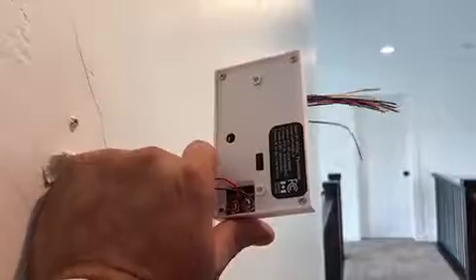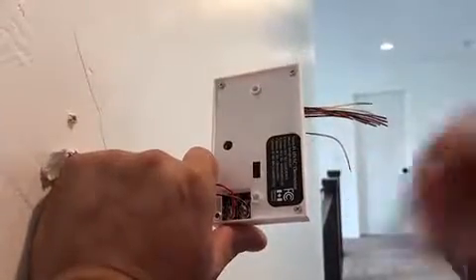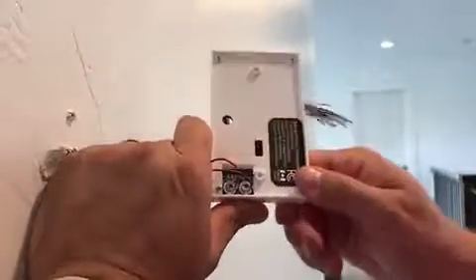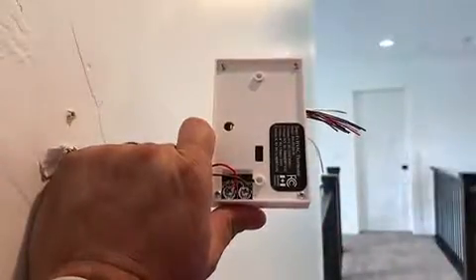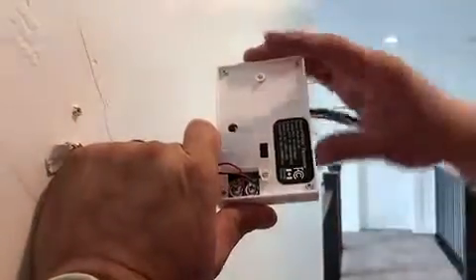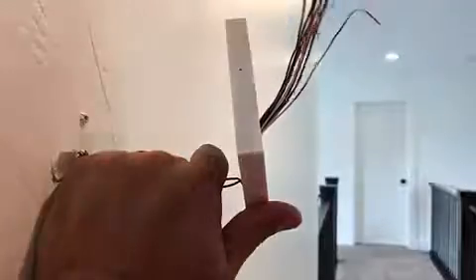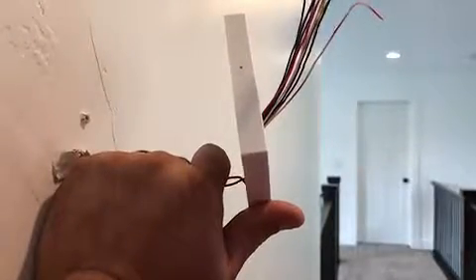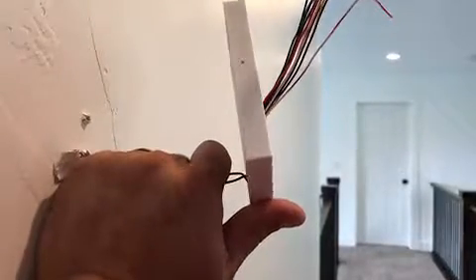an existing wire that's coming up. Let's say you just have heat in that place or whatever. In this case, connect it to a transformer, and I just need 24 volts right here, just like all the HVAC equipment. And then this is going to be able to send that powerful signal down through 2 flights, or through 2 stories, and down to the control room.